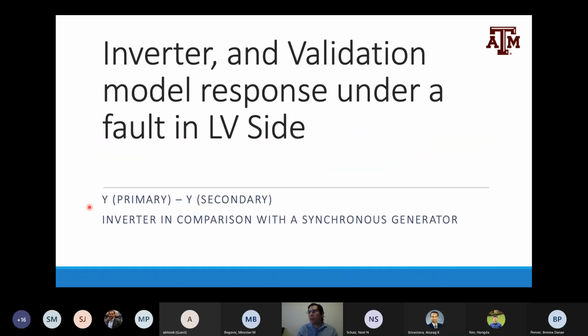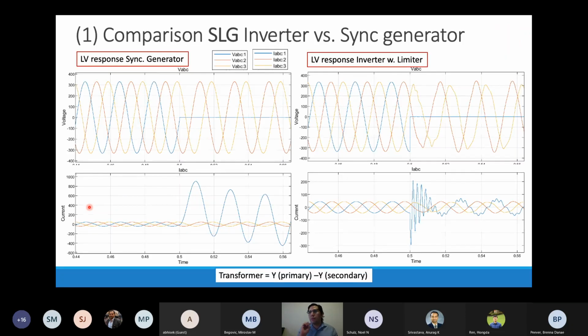So here I'm showing the inverter validation model under different faults. On both figures, which I'm taking from the previous figure where I took the measurements, we are contrasting how a synchronous generator behaves on the left-hand side, the voltage and the current at the moment of a fault, which in our study case, as I mentioned, is a period of 5 seconds, which is here. And on the right-hand side, I'm contrasting this to our inverter model, including the voltage and current limiters that we implemented. And it happens at the same time.